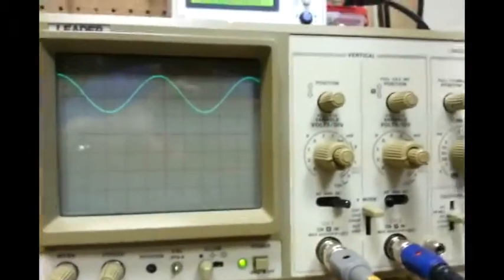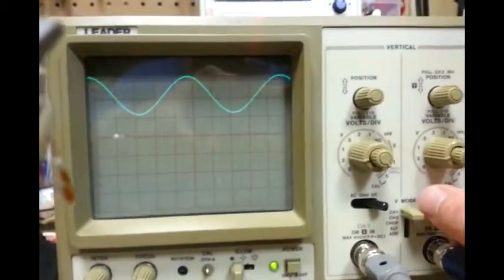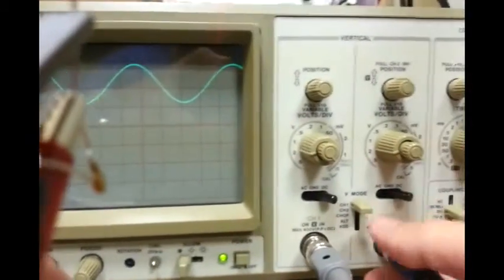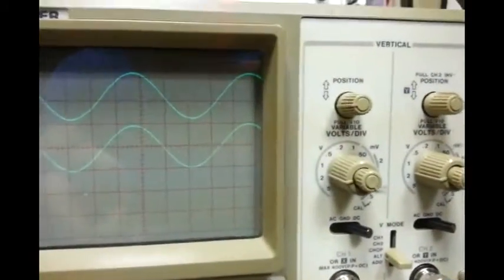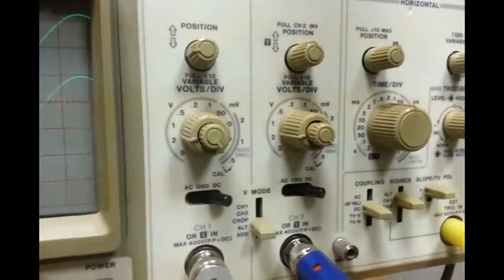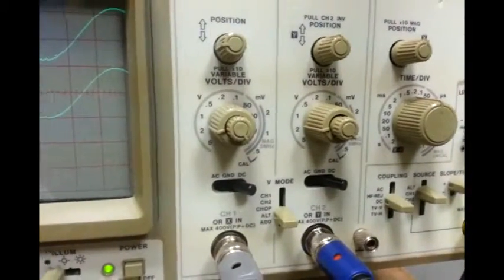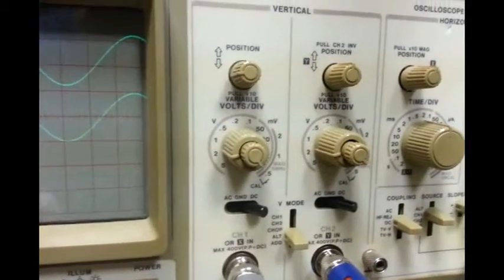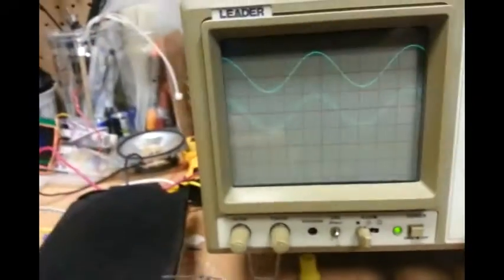So, let's go over here and put this one on to DC. So, both these couplings are set to DC. And let's alternate. Oh! So, we discovered that if you put the coupling on AC, it will remove the DC component of the signal on the screen. But I do still have that 2V offset on there. But these are both coupled on the DC. So, they're showing the offset. So, what happened here?